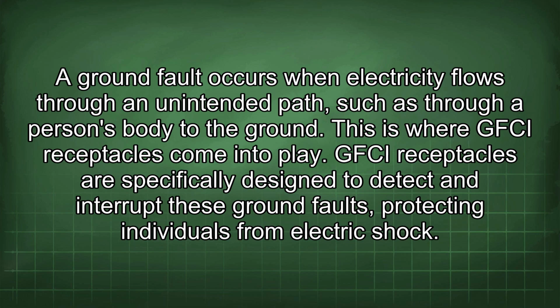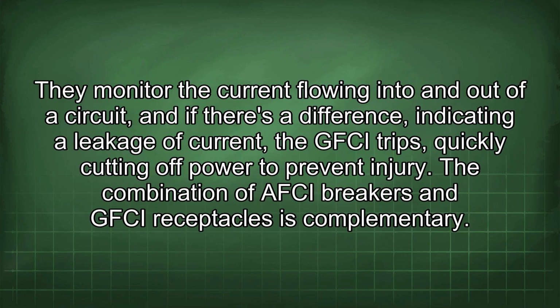A ground fault occurs when electricity flows through an unintended path, such as through a person's body to the ground. This is where GFCI receptacles come into play. GFCI receptacles are specifically designed to detect and interrupt these ground faults, protecting individuals from electric shock. They monitor the current flowing into and out of a circuit, and if there's a difference, indicating a leakage of current, the GFCI trips, quickly cutting off power to prevent injury.